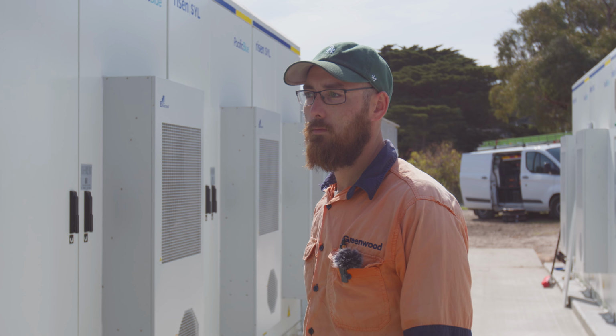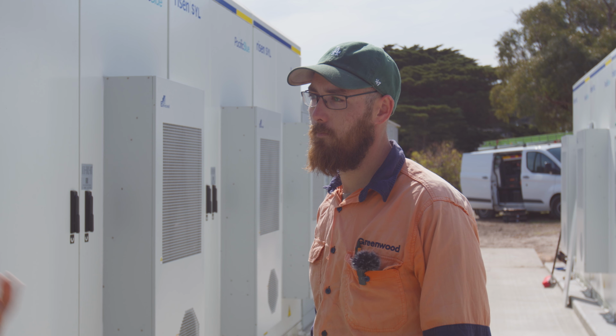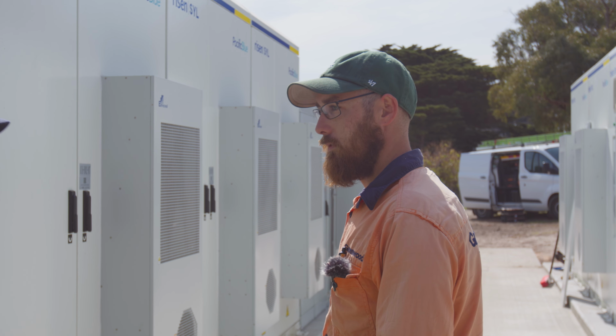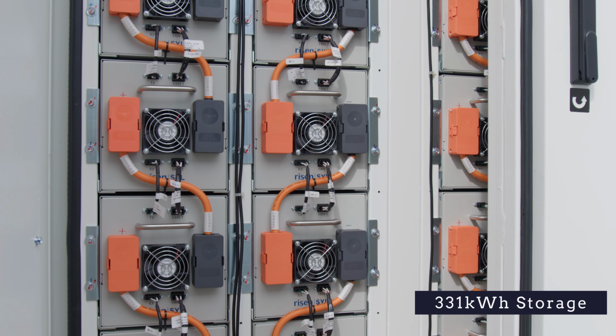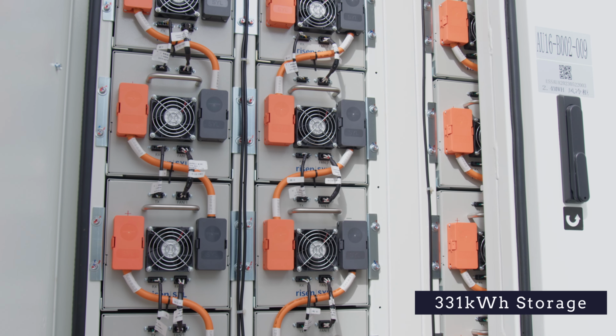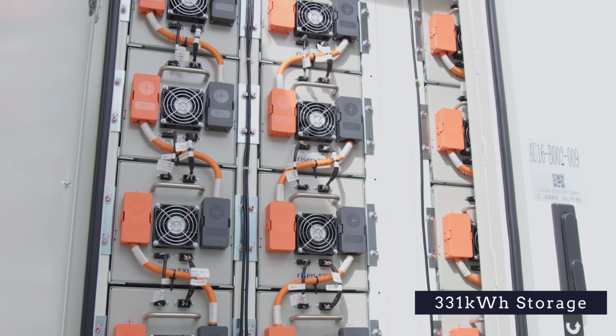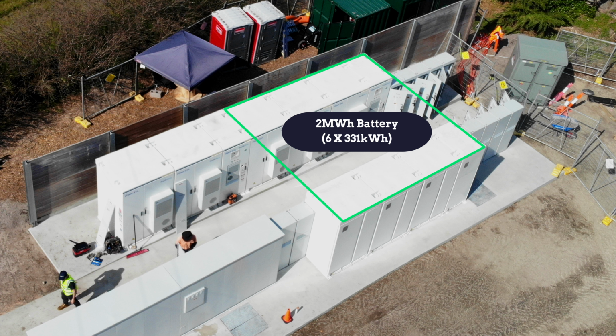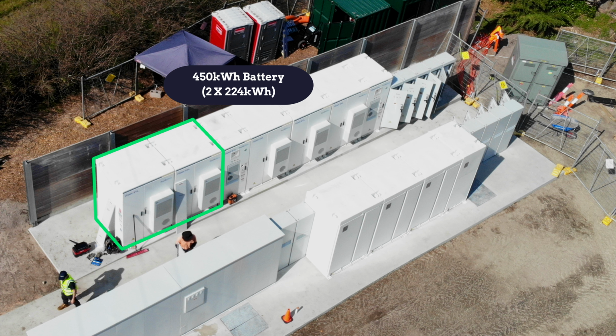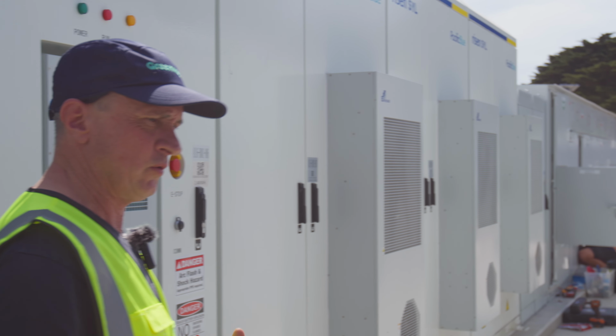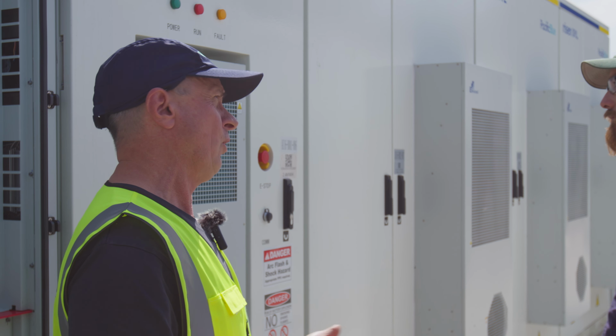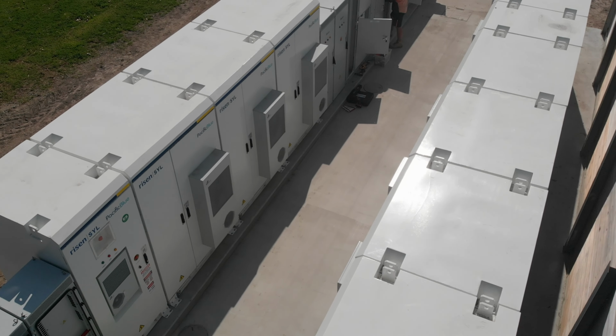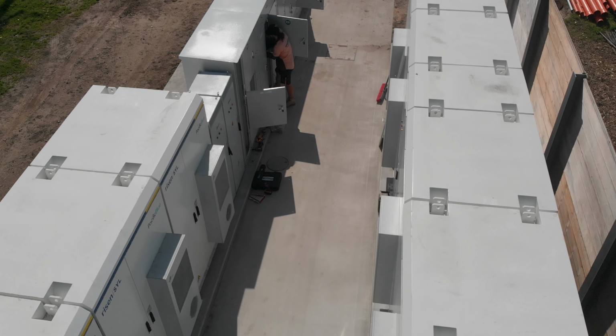Right, okay. Now the battery storage component here, cumulatively, what are we talking about in megawatt hours? Well, each one of these cabinets is 331 kilowatt hours storage. 331? Yep. Unusual number. It is a strange number. I thought that myself. So there's 6 of those. And then down the far end over there, we have a further 2, which is on the separate NMI. Those 2 are 224 kilowatt hours each. For those guys out there who mostly do solar, there's no solar on this site at all. These inverters are specifically dedicated to the particular battery bank that they're connected to.